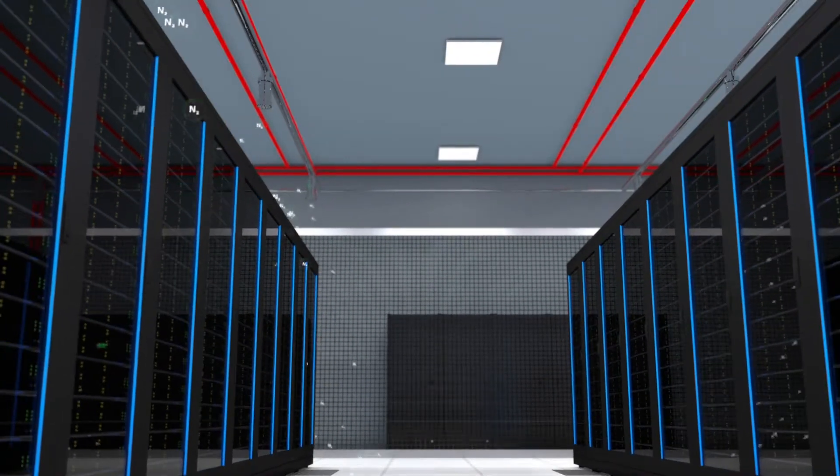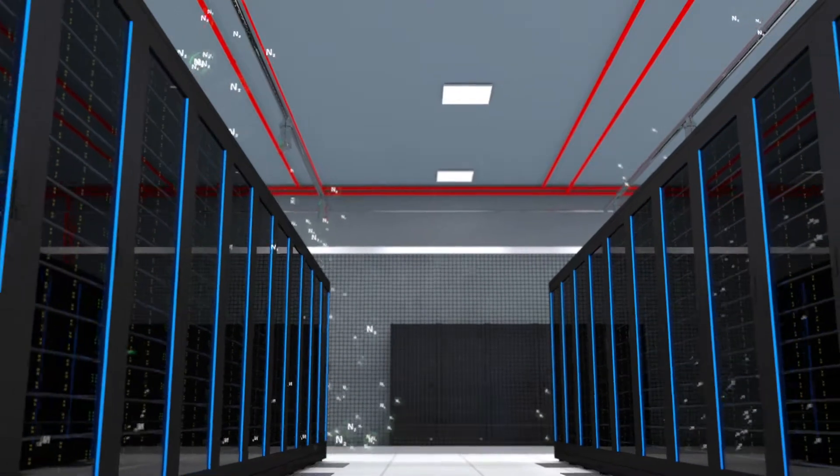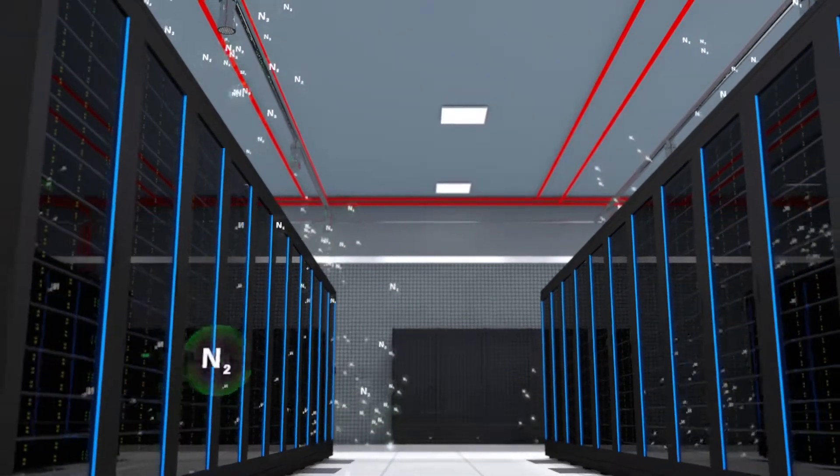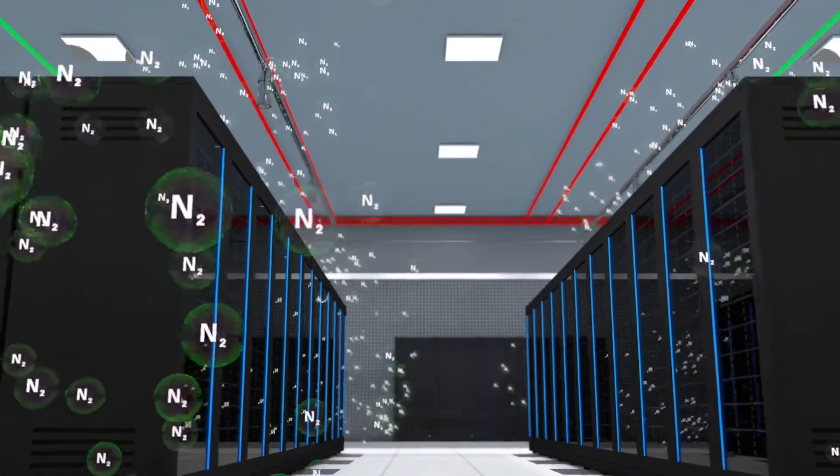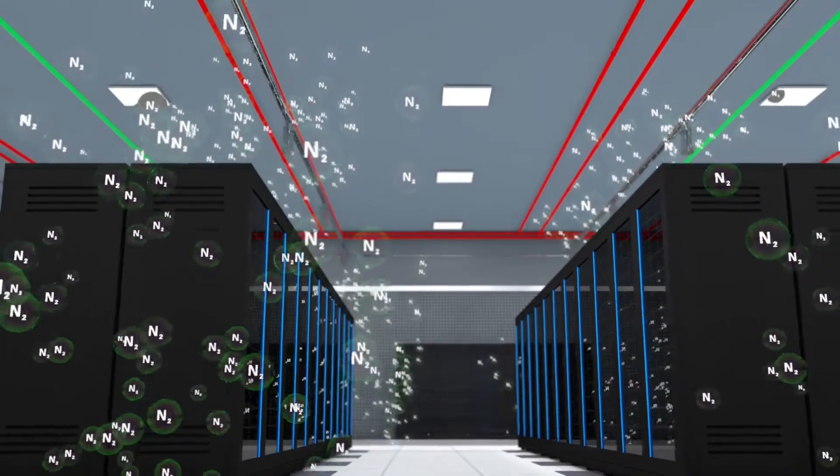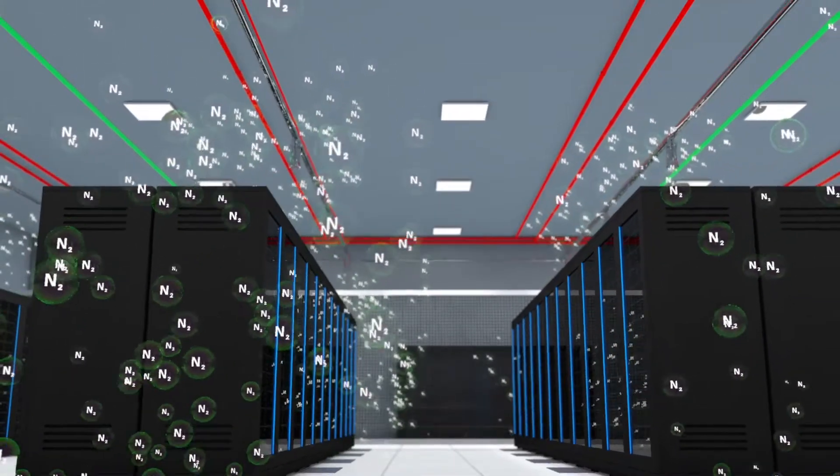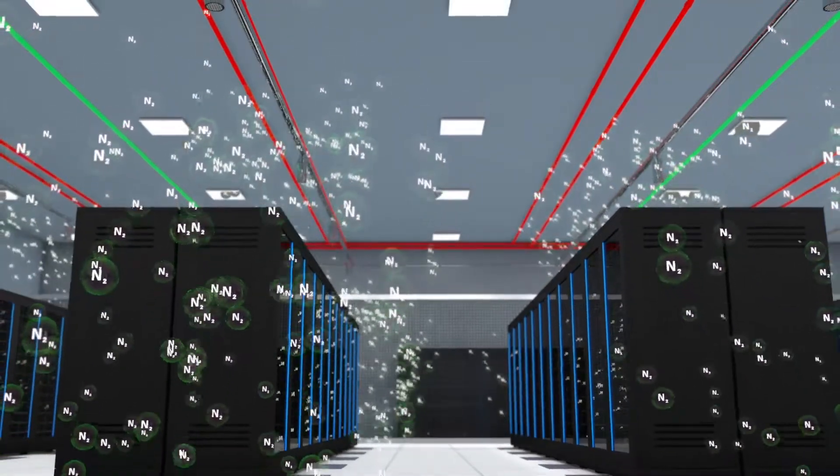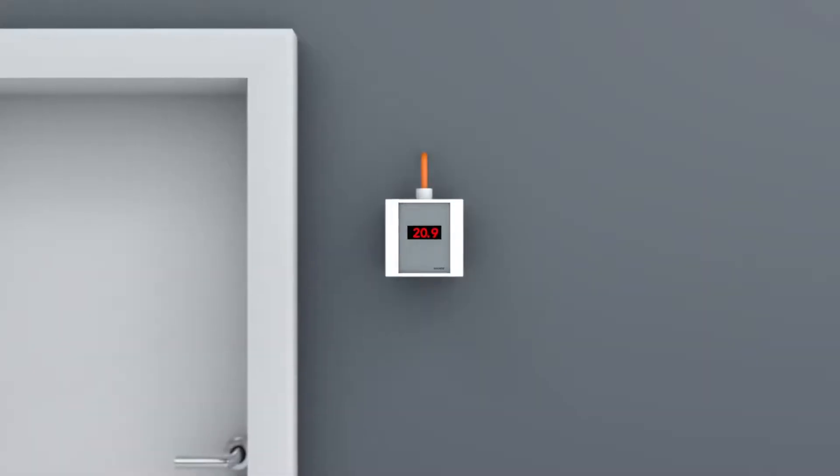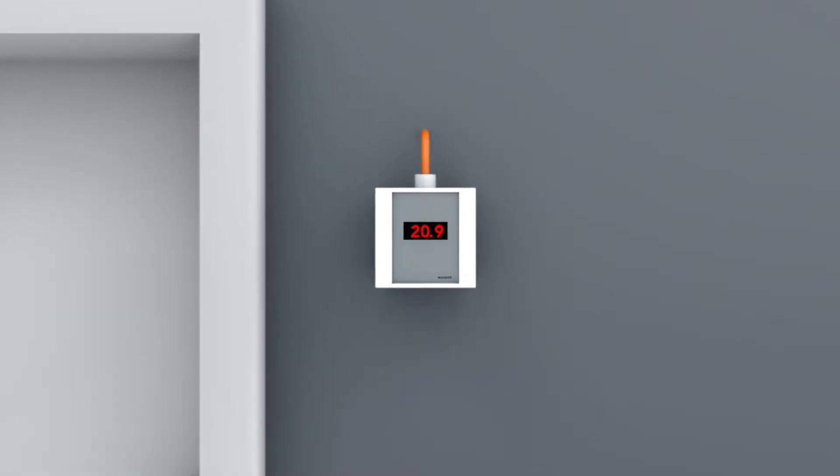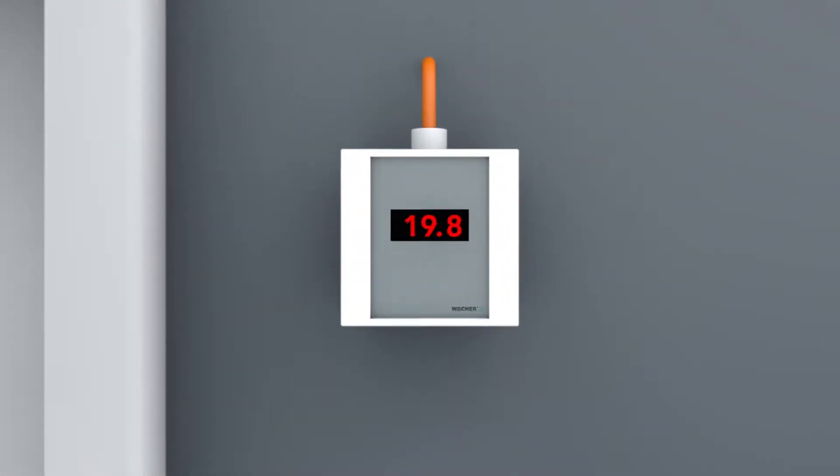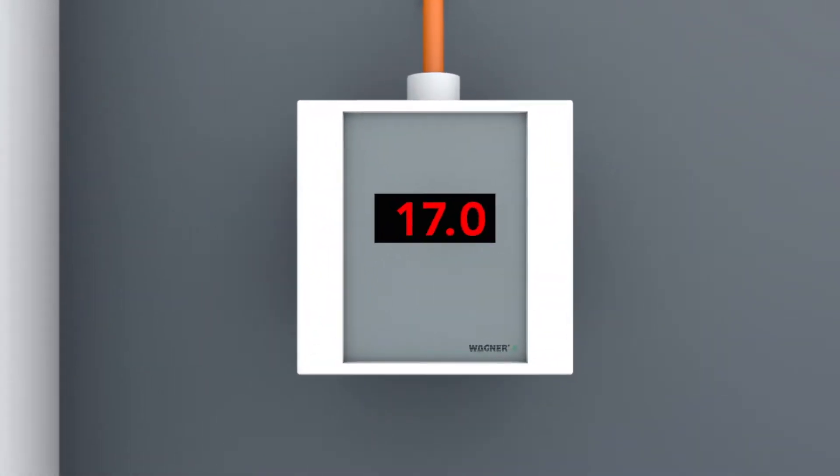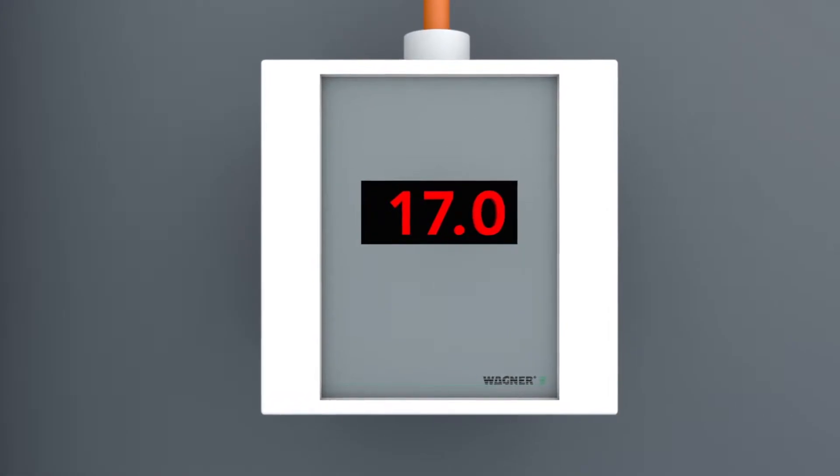The gentle introduction of nitrogen means that the fire behavior can be significantly reduced. As a rule, the fire does not spread further and, in the best case, the fire is extinguished. The oxygen level in the protected area is lowered from 20.9% by volume to 17.0% by volume.